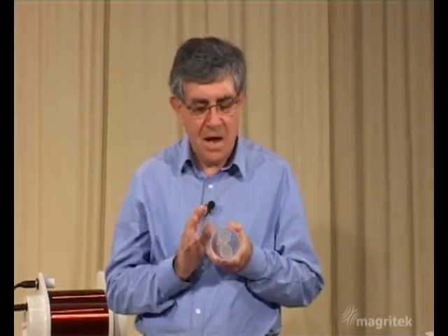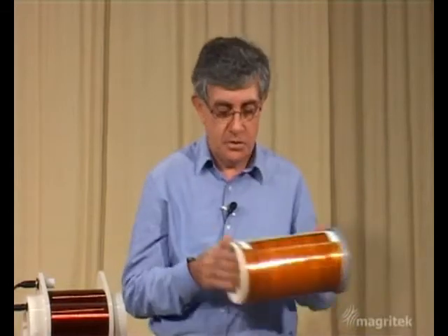Now imagine if we could make that magnetic field vary linearly along the axis where the 2 tubes are separated. In that case, we'd have a very simple relationship between frequency and position. In fact, our frequency axis would also be a position axis. How could we do that? Well, we have the gradient coils.